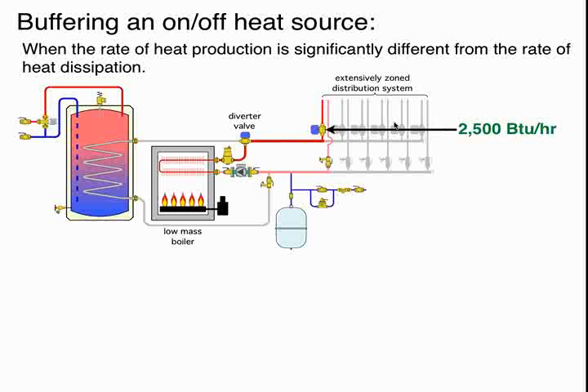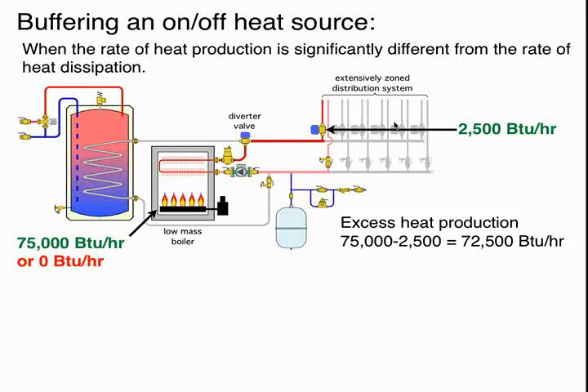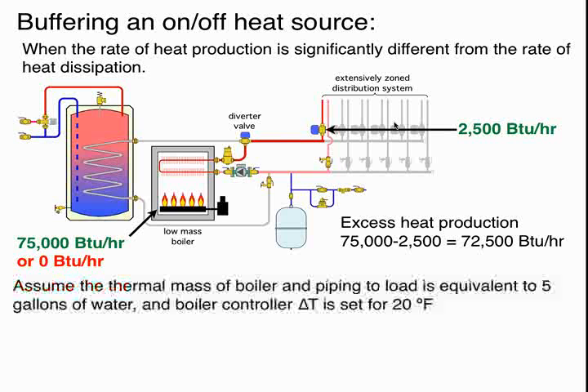So let's put some numbers to this scenario. Let's say we have a load of 2,500 BTUs per hour requiring heat, but our on-off heat source, this boiler, is either zero output when it's off or 75,000 BTUs per hour when it's on. All right? So we're generating heat at 75,000 BTUs per hour, but we're only taking heat away to the load at 2,500. So we have excess heat production, 72,500 BTUs per hour.